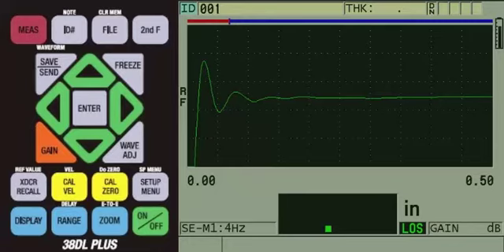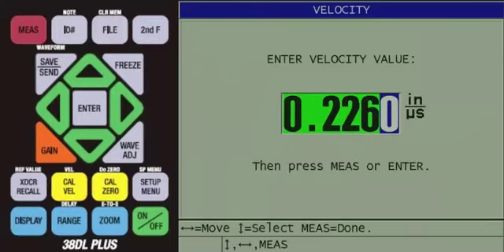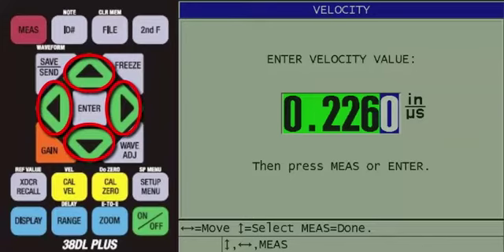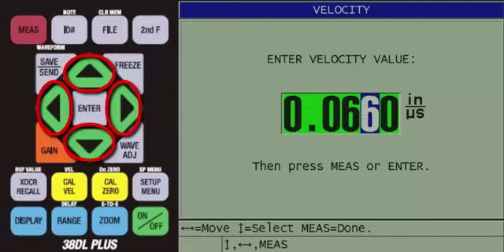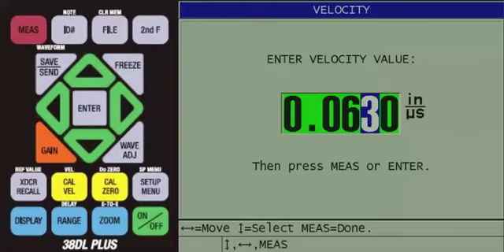To do this, press and release the second F key first, and then press the yellow Cal-Vel key. The stainless steel velocity is shown on screen. Use the arrow keys to change this value to the approximate sound velocity for rubber, which is 0.063 inches per microsecond, or if you are using metric units, it will be 1.600 millimeters per microsecond. Then press the red Measure key.